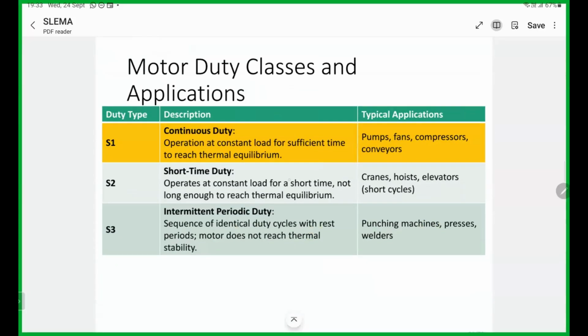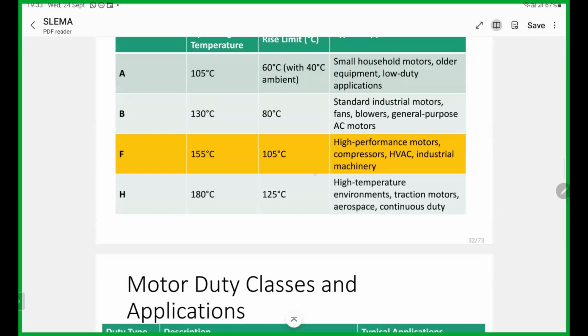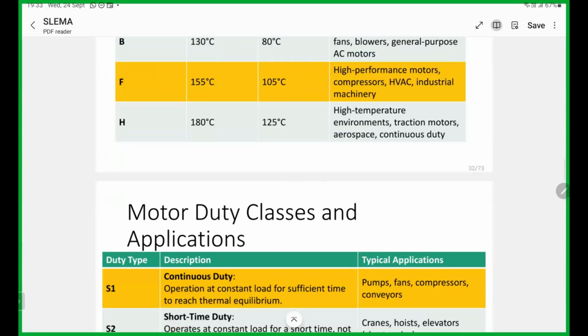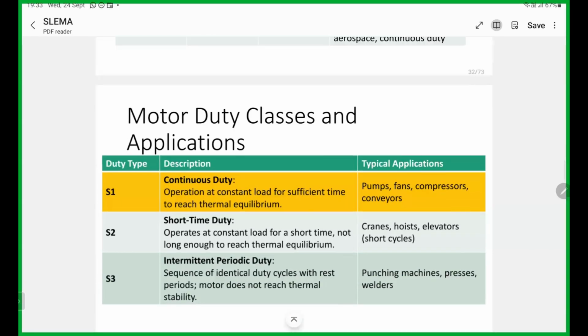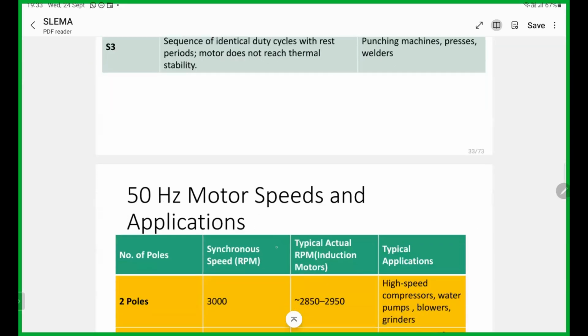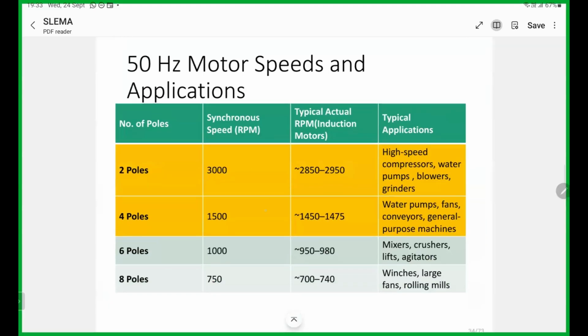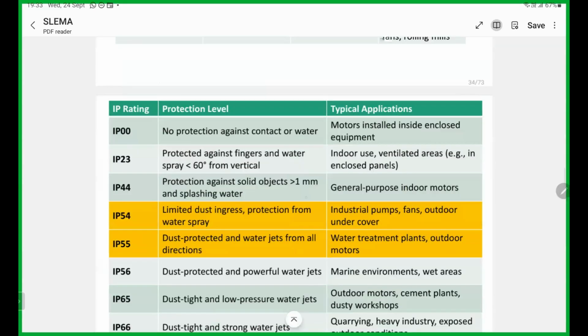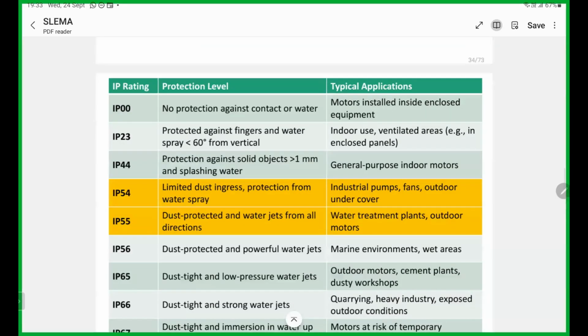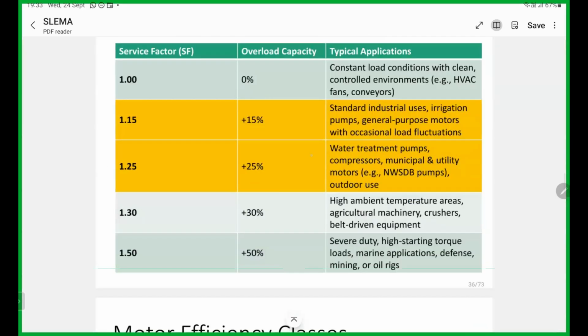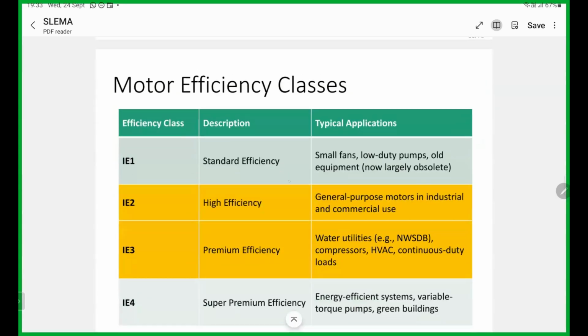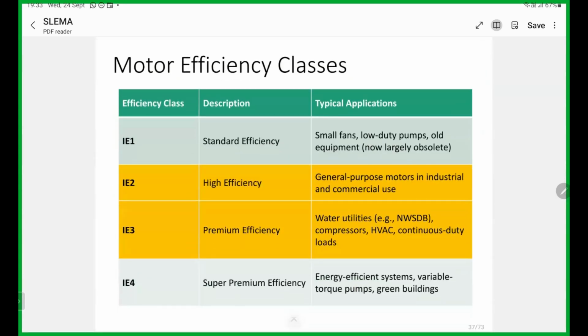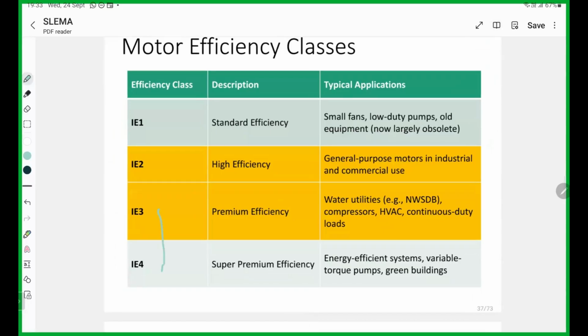This is for selecting a pump motor: insulation class, which is very important, and duty class, that is, one duty or two duty. Then speed, two pole or four pole. Then IP rating, then service factor and motor efficiency classes. Generally, we have to go for at least IE3, or IE3 or IE4. Then you can have better efficiency in the motor.